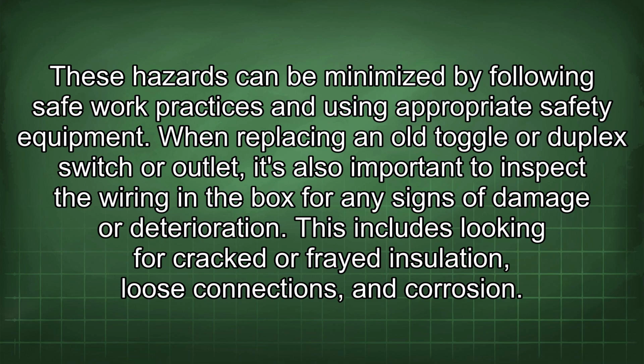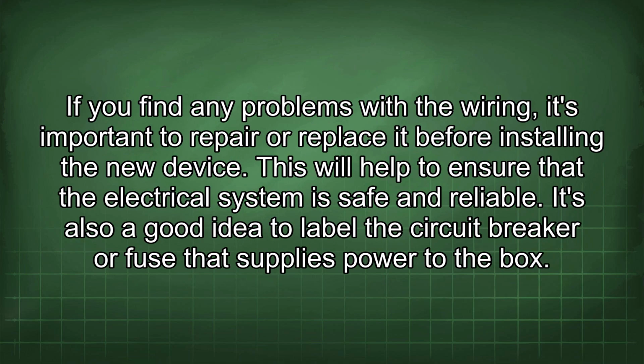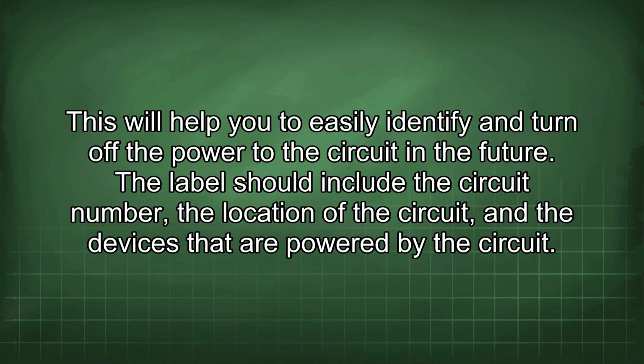When replacing an old toggle or duplex switch or outlet, it's also important to inspect the wiring in the box for any signs of damage or deterioration. This includes looking for cracked or frayed insulation, loose connections, and corrosion. If you find any problems with the wiring, it's important to repair or replace it before installing the new device. This will help to ensure that the electrical system is safe and reliable. It's also a good idea to label the circuit breaker or fuse that supplies power to the box. This will help you to easily identify and turn off the power to the circuit in the future.